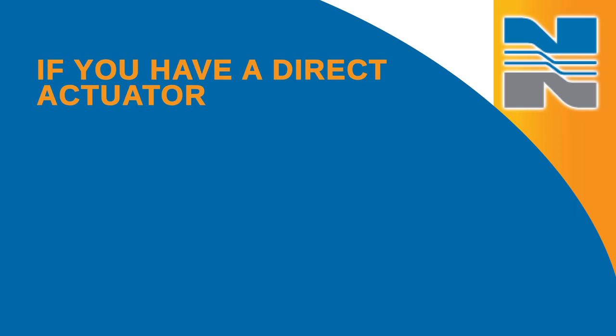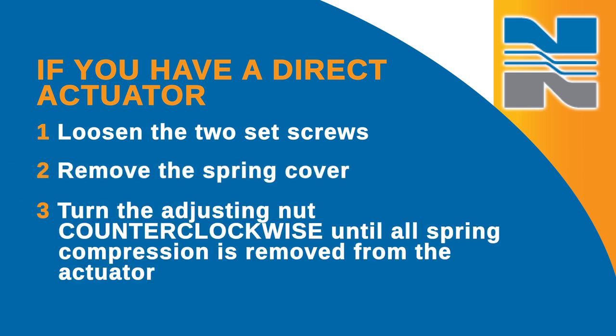If you have a direct actuator, loosen the two set screws, remove the spring cover, and turn the adjusting nut counterclockwise until all spring compression is removed from the actuator spring.